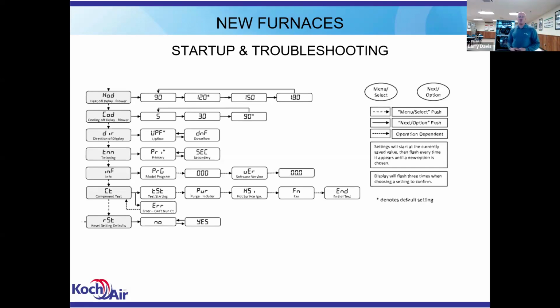Direction of display. You change that from upflow to downflow. It's also called orientation. All that does is flip the 3-segment LCD display upside down, so that if the furnace is in a downflow configuration, you don't have to stand on your head to read it. That's all that does. Twinning. If you're twinning 2 of these furnaces, they have to be the same furnace. You can't twin a new furnace with an old one, and you can't twin an 80,000 with a 100,000. They've got to be the same size furnace. You have to use a twinning kit. The twinning kit has a connection between the 2 boards that allows them to communicate with each other.